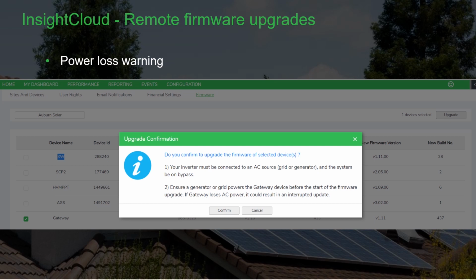Before proceeding with any firmware update, you'll receive a pop-up warning that firmware upgrades to the inverter causes power loss to the grid forming power. If power is lost to the router, the firmware upgrade cannot proceed until the system is put into bypass, meaning either grid or generator will need to be available to bypass the XW Pro and keep the router powered on.